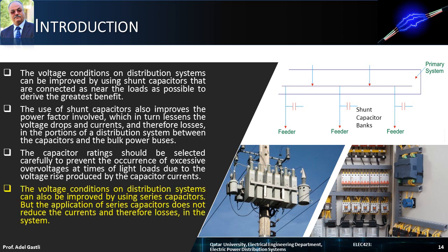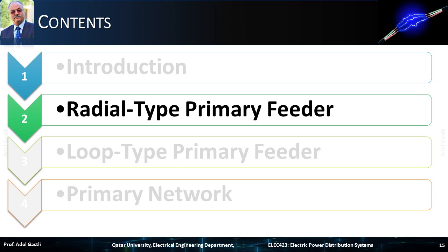The voltage conditions on distribution systems can also be improved by using series capacitors. But the application of series capacitors does not reduce the currents, and therefore losses, in the system. Next, let's see how the design considerations are applied to some types of distribution systems. The simplest, lowest cost, and therefore most common form of primary feeder is the radial type primary feeder. So let's start by studying the design considerations for the radial type primary feeder.